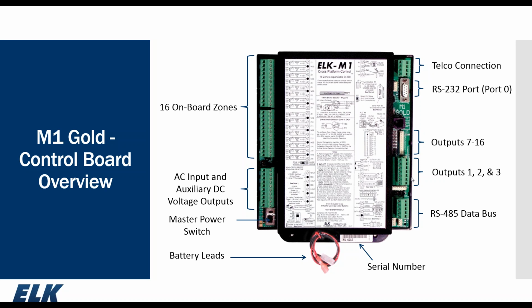The upper right-hand corner is our telco connection, standard POTS line connection there. Below that is the RS-232 on-board serial port. We call it port 0. Below that is a white header pin that we have called J16. This is your low voltage outputs 7 through 16. Next, outputs 1, 2, and 3. And the last one is our data bus, our RS485 data bus. Now we're going to talk a little bit more about each one of these in the next few slides.